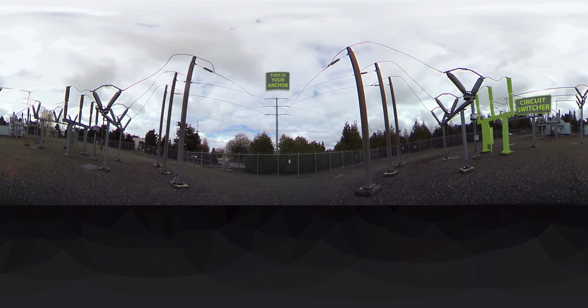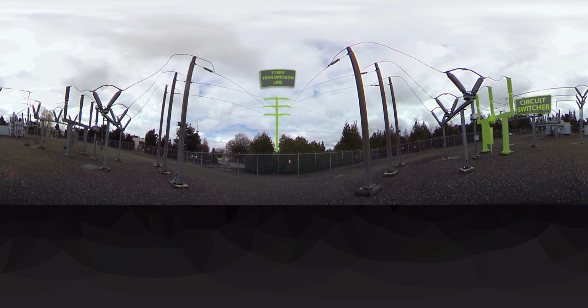Swivel your camera back around and find the 115 kV anchor point again. If a tree were to fall on the right side circuit of that transmission tower, the potential transformer would notice that fault, which would trigger a relay housed in the back of the substation to open the breaker. The activation of the circuit breaker would isolate the right side circuit of the substation. Once isolated, this substation would still be operating from the left side circuit until either the fault clears or maintenance is completed.